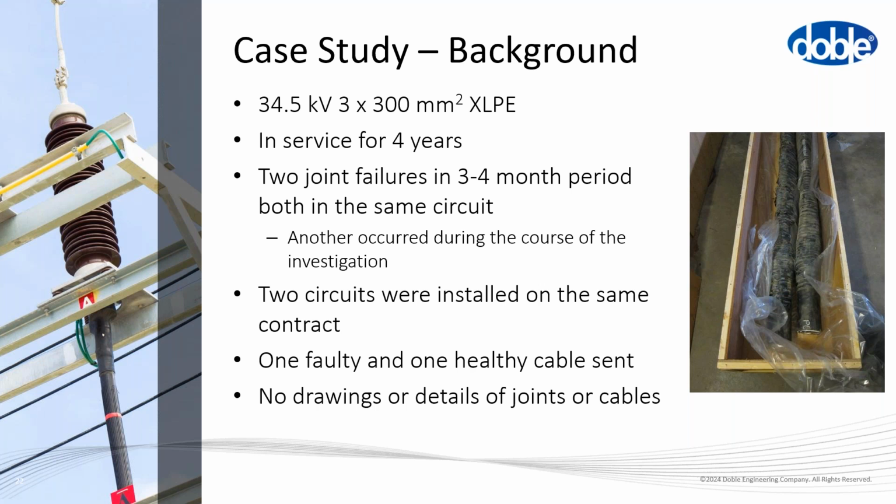So I'm going to give a case study from a few years ago. I think this one's quite nice. It's a medium voltage cable investigation, but it shows a number of the analytical techniques. We use the 5 whys in this one, and it also shows the risk of being shackled to some of these techniques. So in this case, it's a 3-core cable, 34.5 kV.